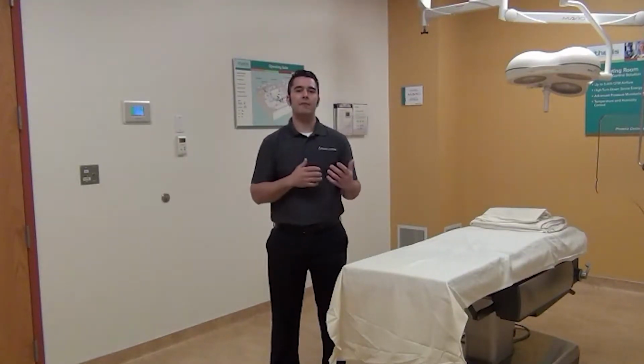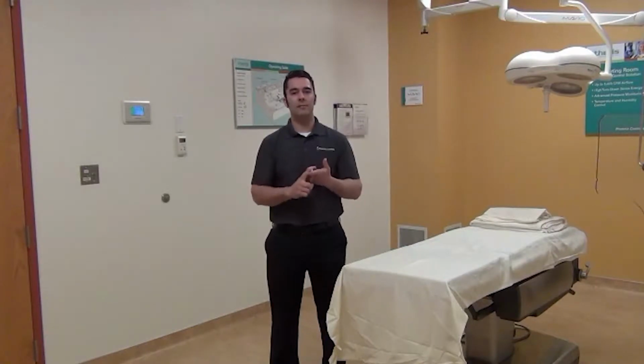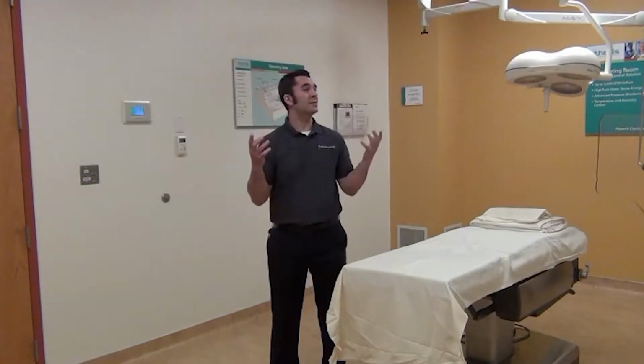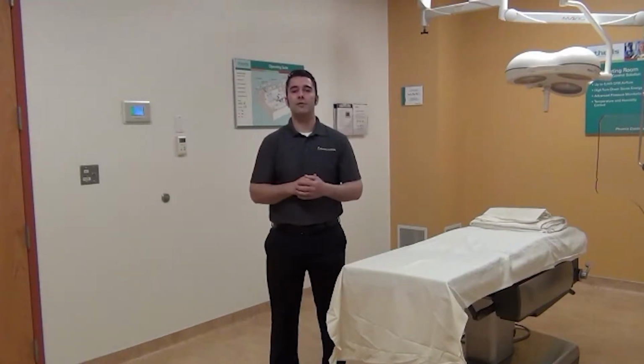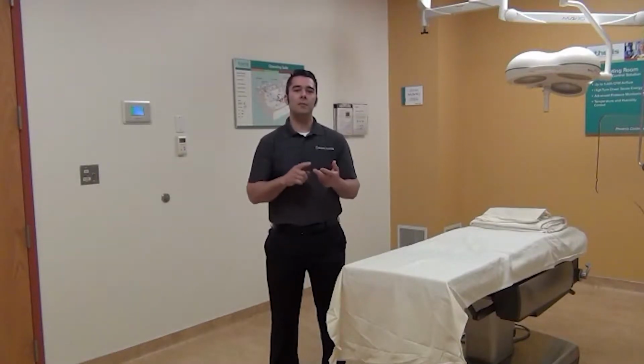The last stop we have in our Phoenix Controls healthcare demonstration suite is the operating room. Now, the main concerns that happen inside of an operating room, again, going back to maintenance, making sure that whatever products are chosen to be put in here do not have to be maintained at all, because in this type of an environment, you really don't want to be shutting it down and cleaning sensors out every few months. Secondly, making sure that the pressurization inside the room remains constant at all times to guarantee the pressurization.